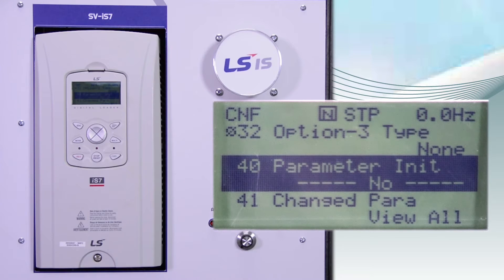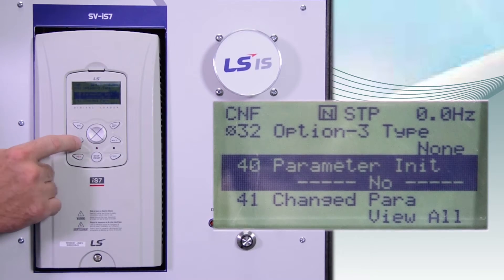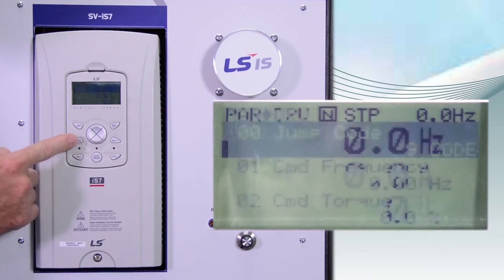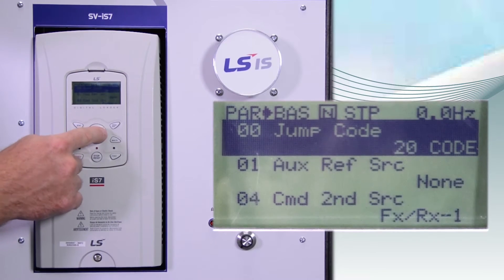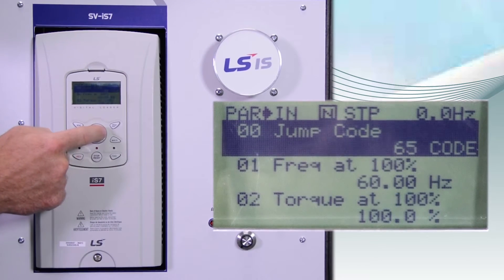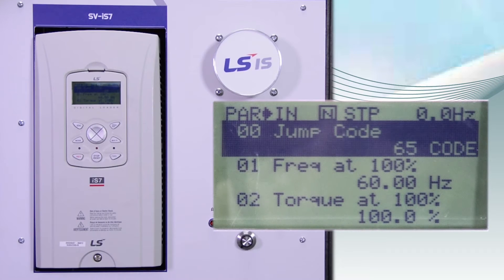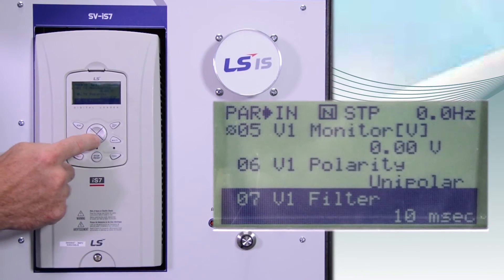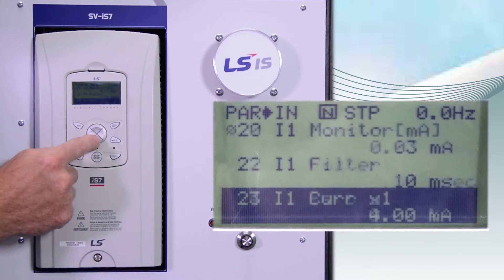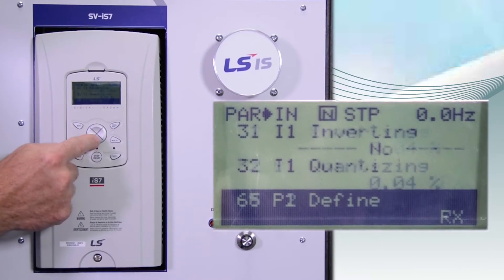To program the different digital inputs, press the MODE button. To get back to the parameter menu, starting in the DRV group, press the right arrow until we get to the IN group. To find the parameter associated with the digital inputs, we'll start at IN65.